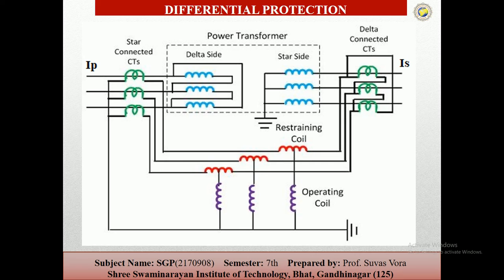For example, if both the currents I1 and I2 are increased, अगर external fault है तो I1 and I2, it means the primary side and secondary side both the currents are increased and thereby the restraining torque increases, which prevents the maloperation. So this is the basic principle of the differential relay.